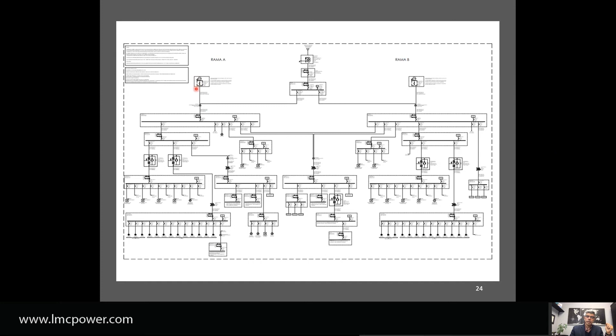Now let's assume the generator kicks in. That will generate a transient, a spike in energy, going into this electrical panel. Here we have a surge protector, category B. They oversized it a little bit - category B was going to be between 100 and 150 kA, but they said let's just go 200. It could have been 150 or 100, but oversizing a bit more, like we talked about with the drain, isn't an issue. This kind of customer merits that kind of protection.